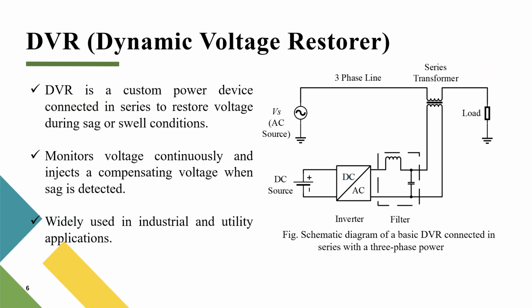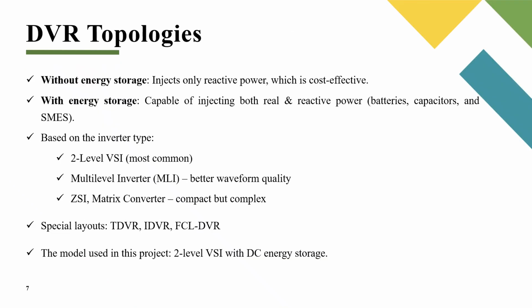DVR, dynamic voltage restorer. A DVR is a series-connected device used to inject compensating voltage during sag or swell conditions. It is triggered only when voltage drops below a reference level. In this project, its behavior was modeled and simulated to assess its role in stabilizing load voltage.